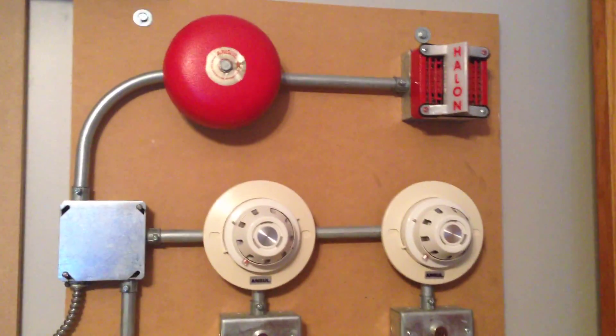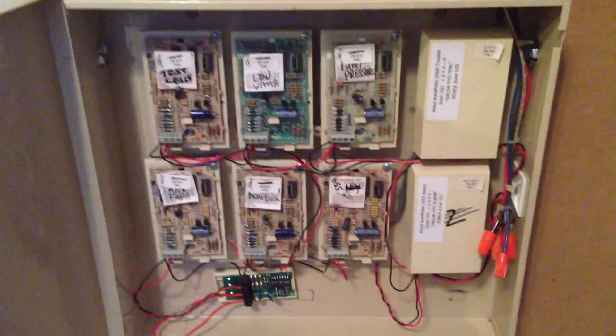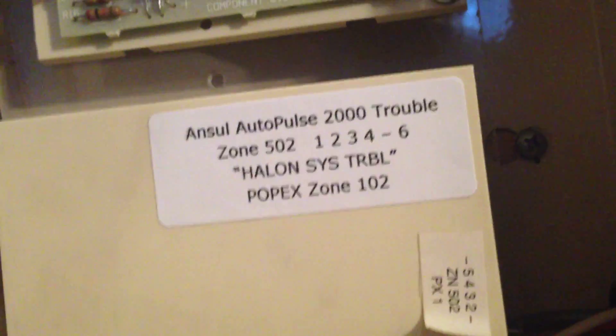We haven't seen this in one of my videos in a while, but it's the same Halon system that's always been here, with the addition of this Radionics monitoring box down here at the bottom, which has lots of modules in it. All of these report to an expansion module within the DMP panel. All of these are original to that building, except for these two over here, which monitor the Ansul system.